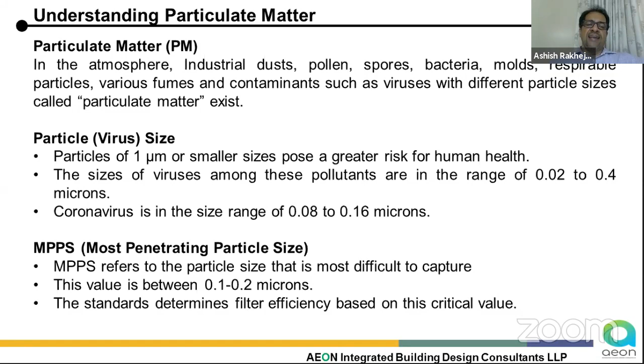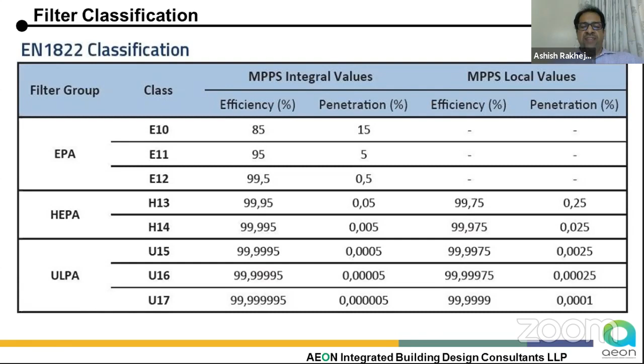But having said that, it's not possible to put HEPA filters everywhere - there are constraints with existing systems. So it's not like if there's no HEPA, nothing can be done. A good filtration, which may not be HEPA, in an existing setup can also help alleviate the problem, if not completely remove it. HEPA may have a filtration efficiency of 99.95% going up to 99.995%, but lesser than that we're talking of a filtration efficiency from 85% to 99.5%. So HEPA alone - yes, it's desirable to have, but is that the only solution? No. Experts could help you look at those areas.